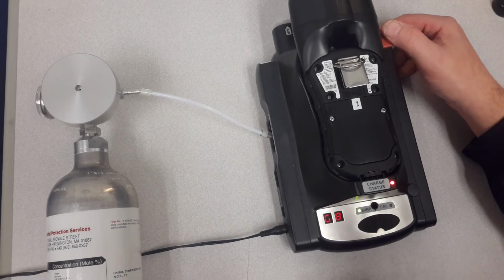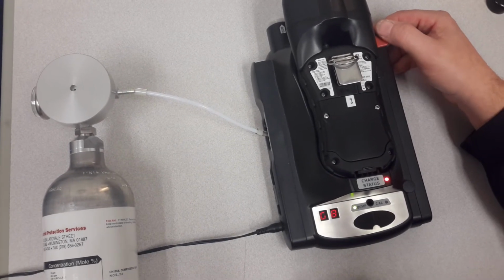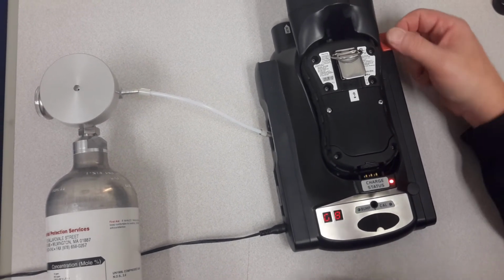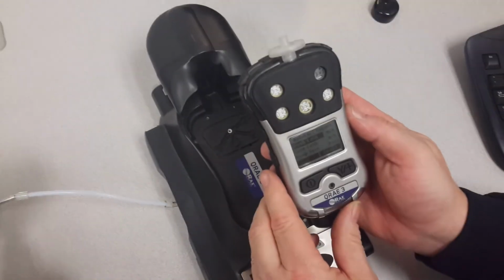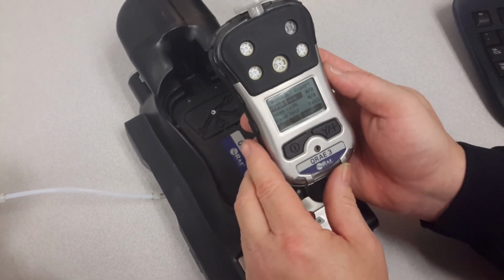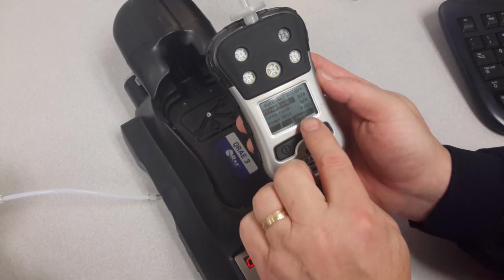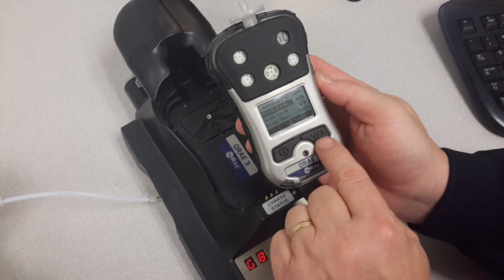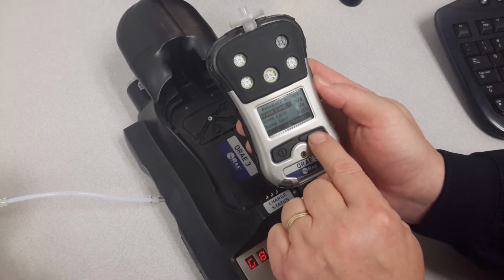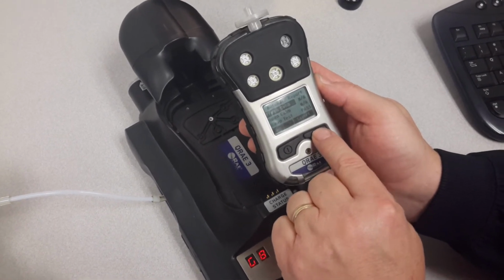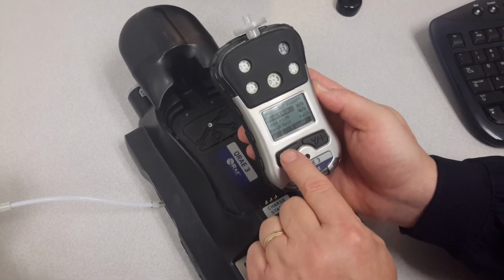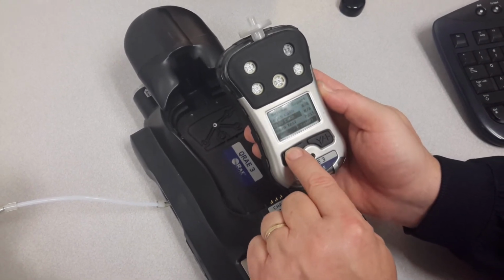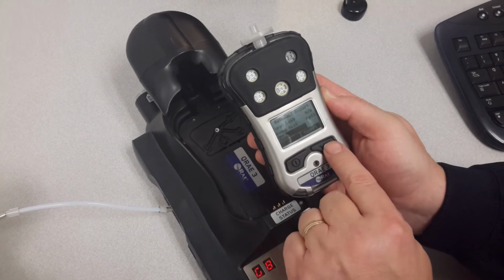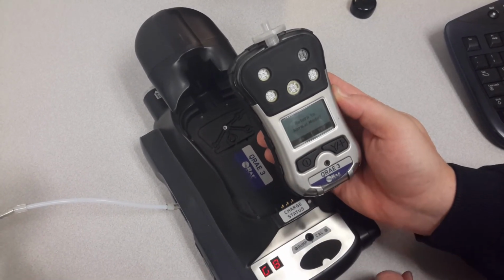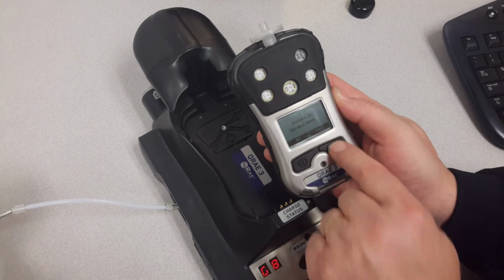To end the test, all you do is open up the Cradle by pressing this red button down, and you go ahead and take the machine out. And if you note here, you see that the bump test passed. Okay, all you do is select the Y plus sign for select. I'm sorry, yeah, my mistake. You gotta actually use the down button to exit, and then select. And then you return to normal mode, you'll say yes.